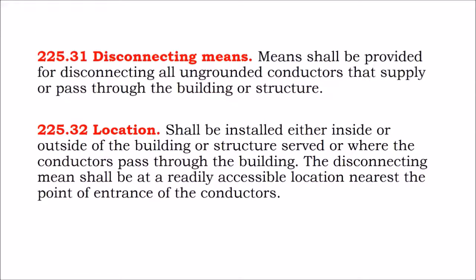Disconnecting means shall be provided for disconnecting all ungrounded conductors that supply or pass through a building or structure. So the question is, does your disconnect need to disconnect the neutral? The answer is no. In fact, sometimes you should not disconnect the neutral.